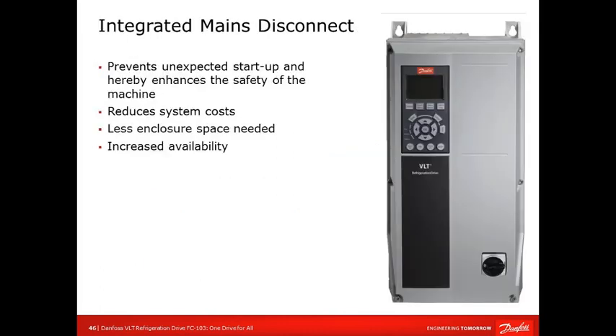Also, just to share, here's a NEMA 12 with the integrated mains disconnect. Again, we're trying to protect not only the safety of the equipment, but also someone performing maintenance on a piece of equipment. Obviously, this will increase the safety of not only the machine, but also the operator working. And the advantage of what we're showing here is that we're not taking a VFD and putting it in a panel so that now you have a VFD panel. You're actually getting the VFD in its own enclosure with the mains disconnect.